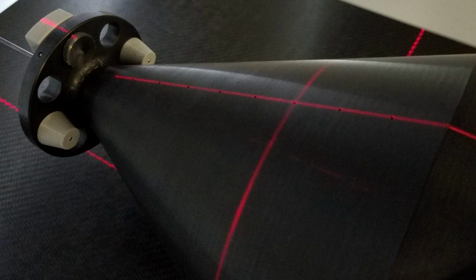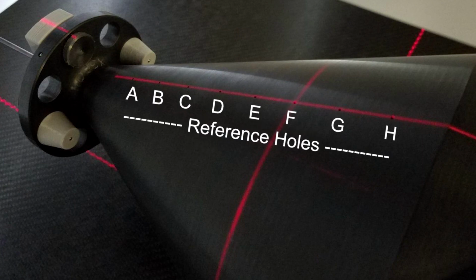and profile. On the exterior of the imaging cone are 32 calibration holes, which are also called reference holes, arranged in groups of 8 holes on the top, bottom, and sides of the cone. From the camera's point of view, we call the top set of holes north, the bottom set south, and the other sets are east and west.